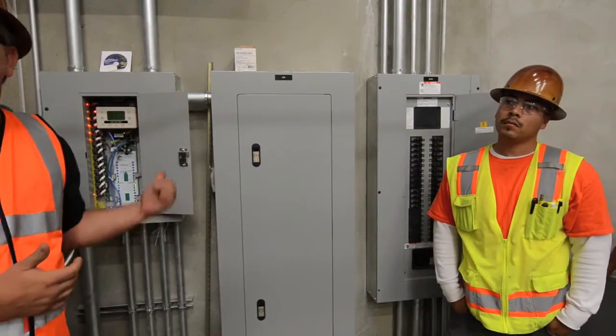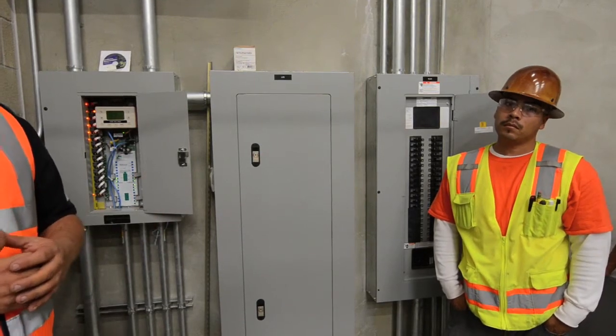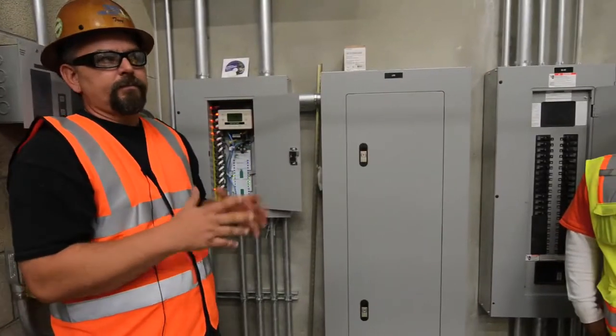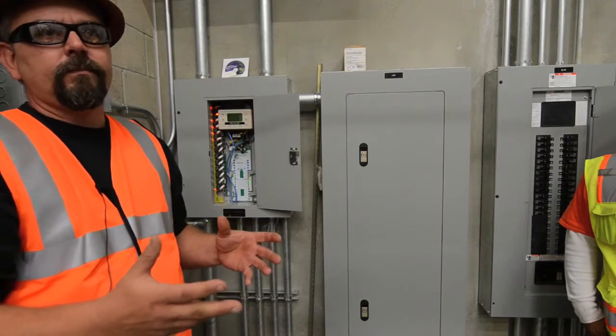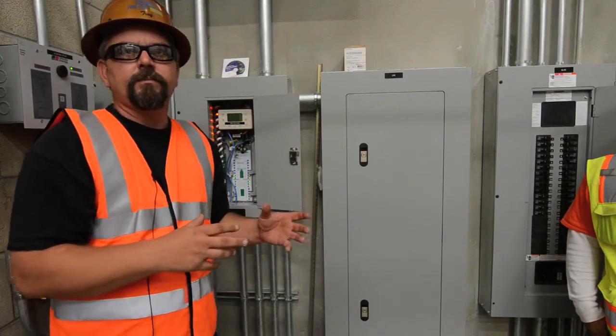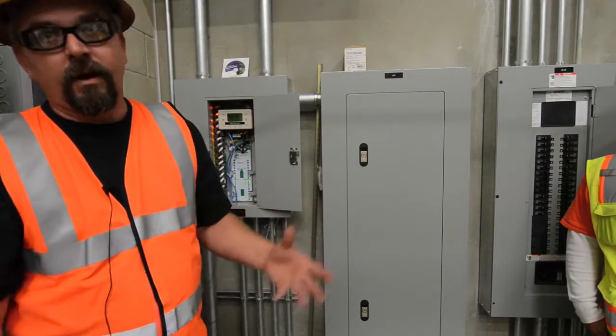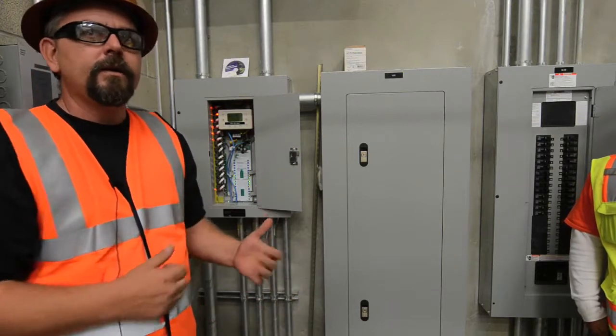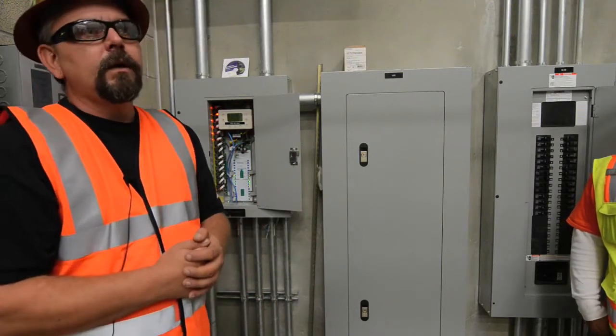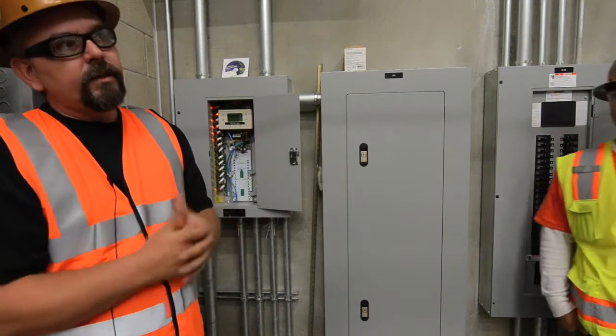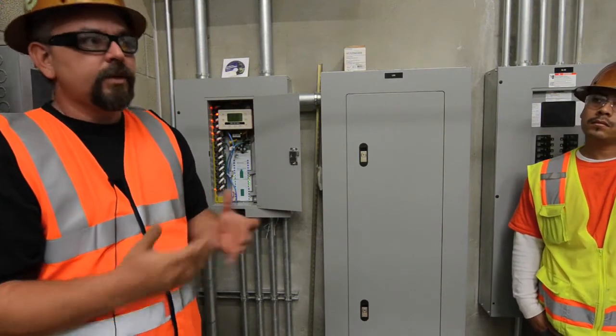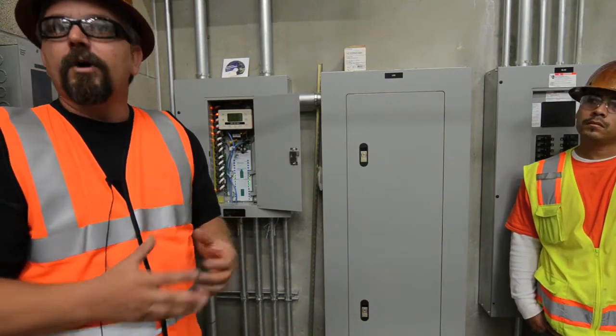So when you have a failure here, your lights stay on. That's one of the nice things about LC&D, it's completely opposite of the older technology. When there's a failure with the old tech, the lights aren't working. When you have a failure here, they're going to be on all the time. So you're going to have exterior lights, as a good example, on during the day when they shouldn't be. That lets you know there's a problem.